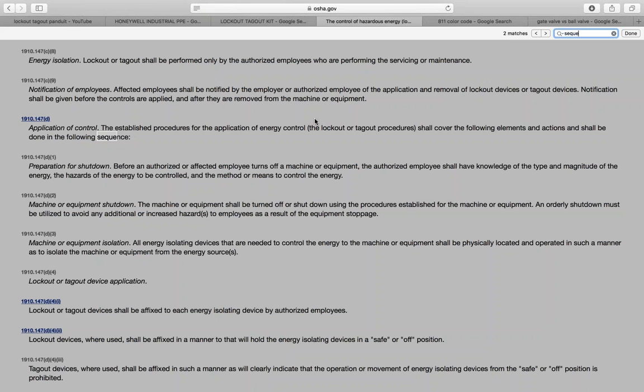And then, if it's necessary to temporarily leave the area, upon returning we've got to retest to ensure that all the equipment's still in a de-energized state. If we leave for the day, we come back the next morning before everybody starts working, we verify that everything is still in the de-energized state, okay?